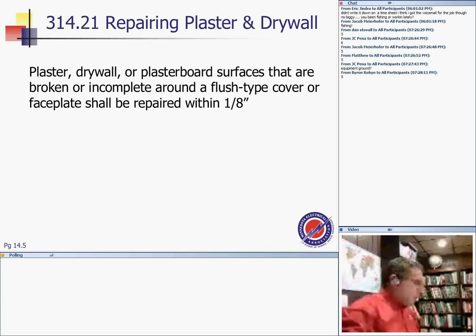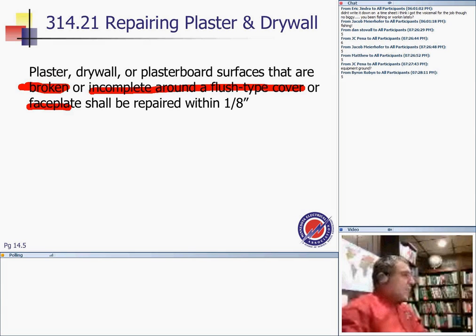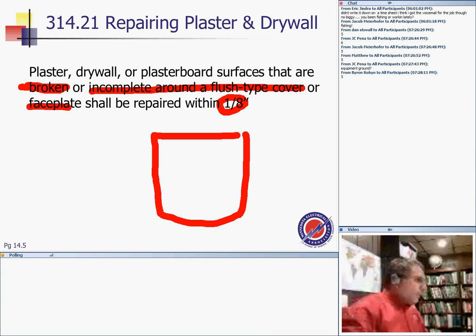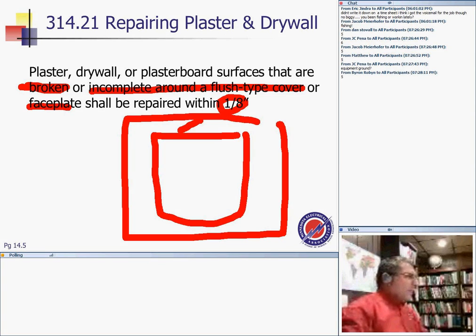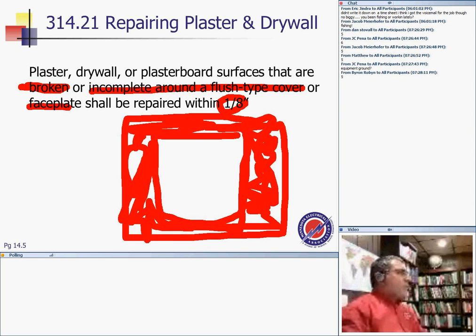So in the exam review that we were doing: drywall, plasterboard surfaces that are broken. I'm not sure how many of you have broken some of these when remodeling. Gaps around the flush type covers or faceplate shall be repaired so there is no gap greater than 1/8 of an inch. So in your device here, this is the box; repair this stuff around the box within 1/8 of an inch.